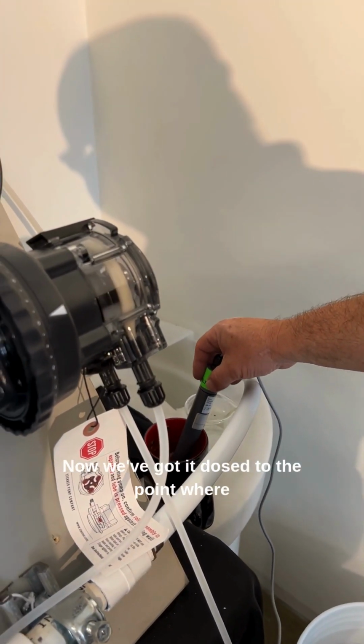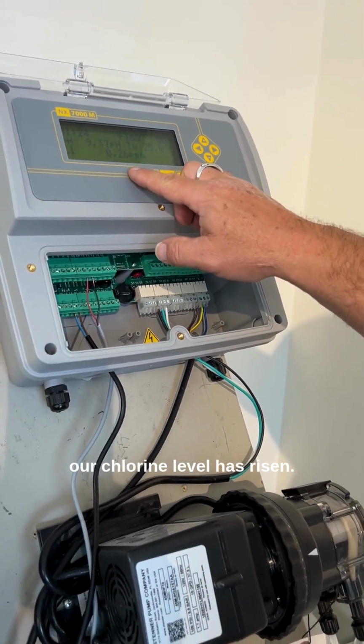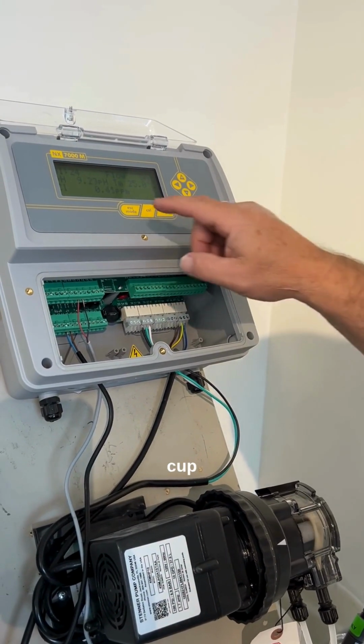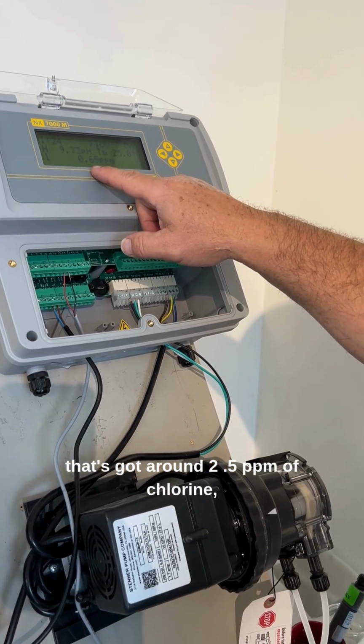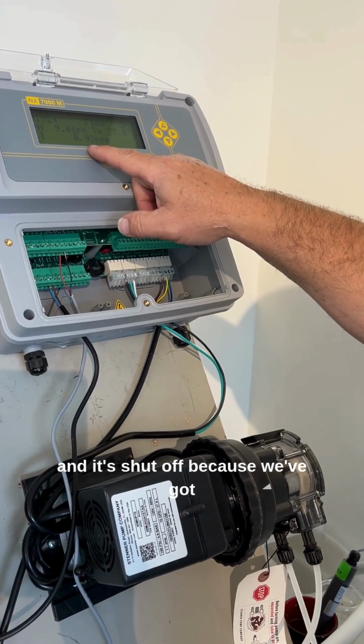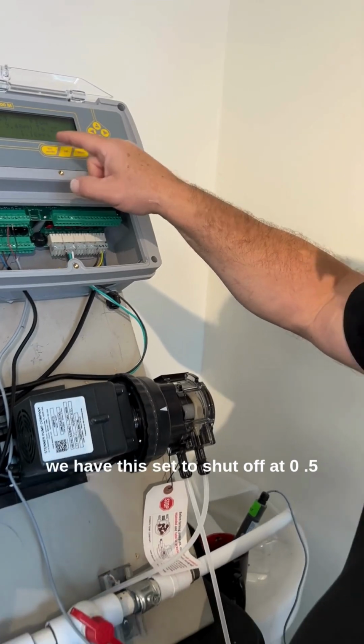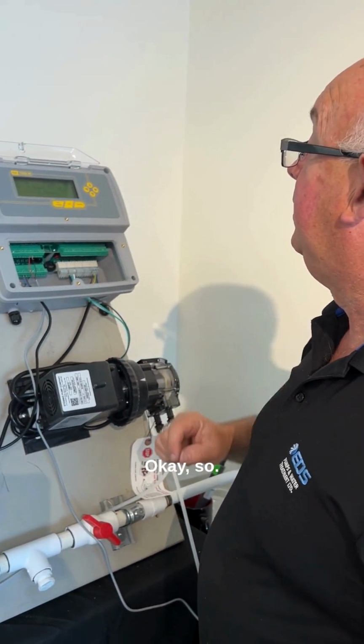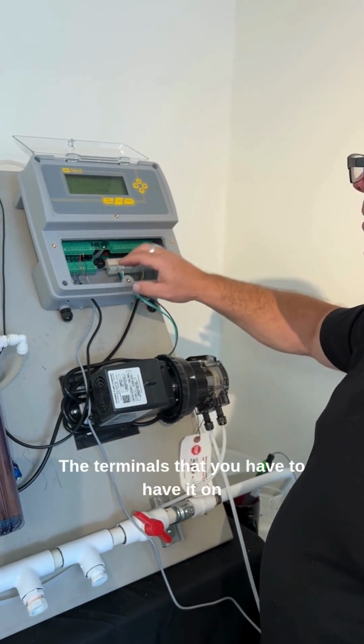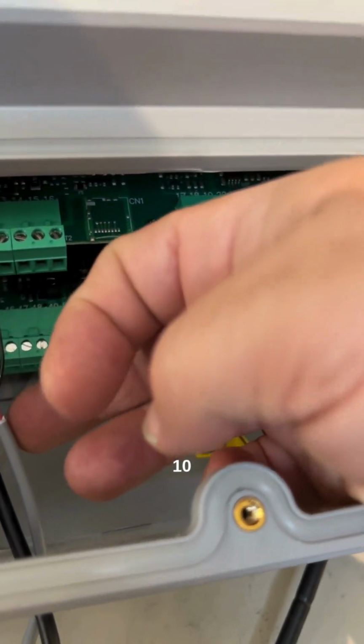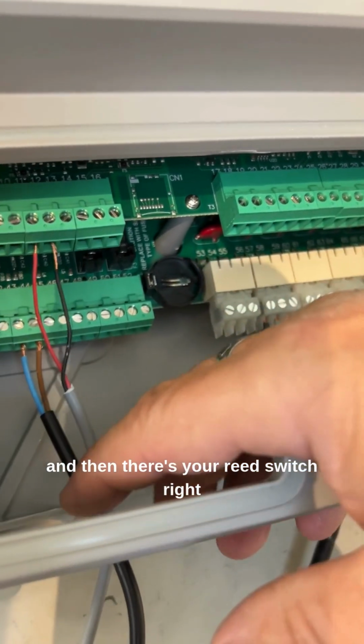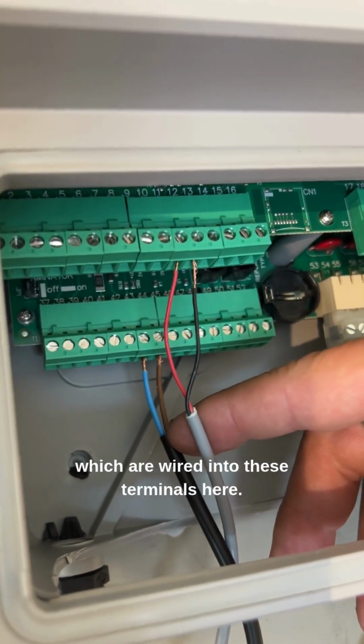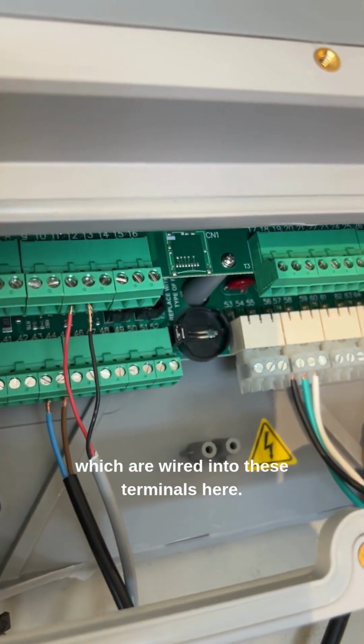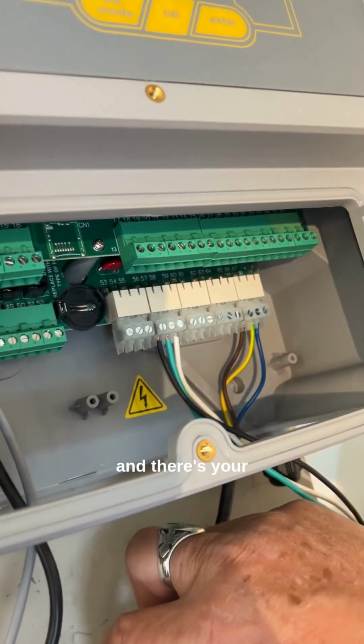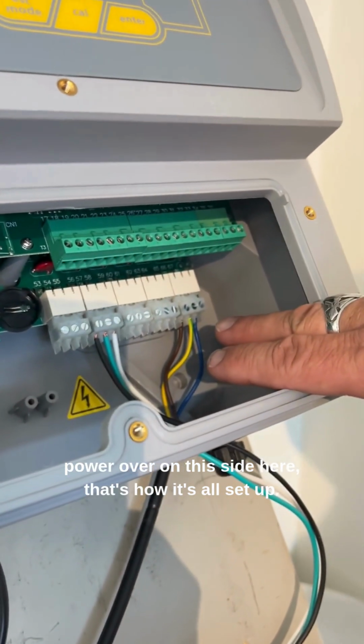Now we've got it dosed to the point where our chlorine level has risen. So I'm simulating that by putting it in that cup that's got around 2.5 ppm of chlorine, and it's shut off because we have this set to shut off at 0.5 ppm of chlorine. Okay. So the terminals that you have to have it on are 10 and 11 and 12. And then there's your reed switch right here, which are wired into these terminals here. There's your pump, and there's your power over on the side here. That's how it's all set up.